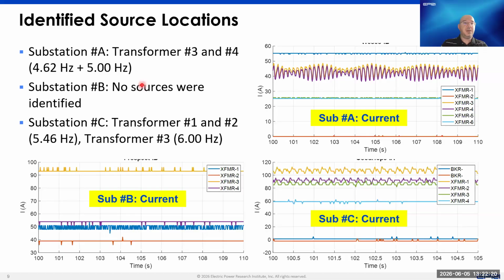For substation B, we didn't identify any source. As you can see here, the data were not indicating that any load within that substation was the source. While here you see from substation A, specifically from these two transformers 3 and 4, that we can see the oscillations with this frequency.